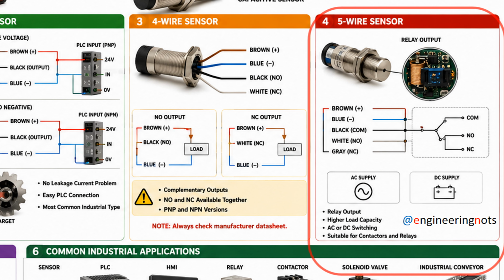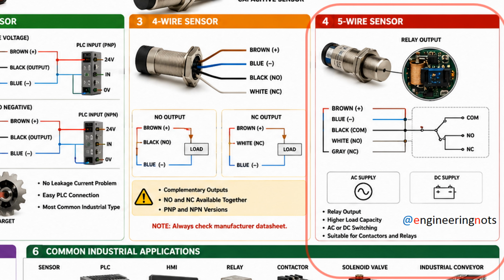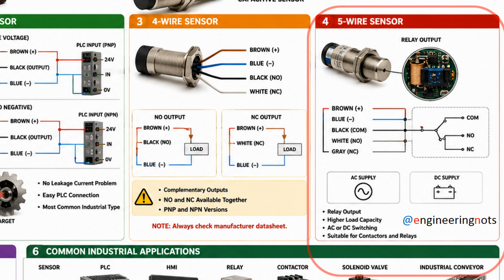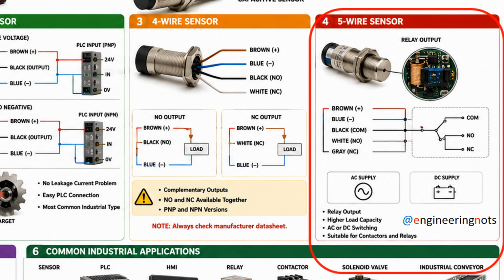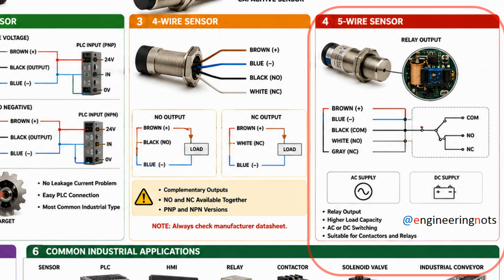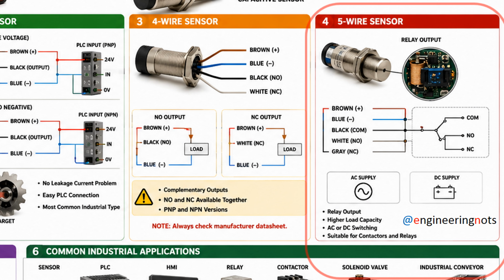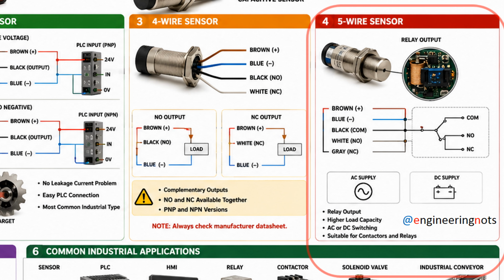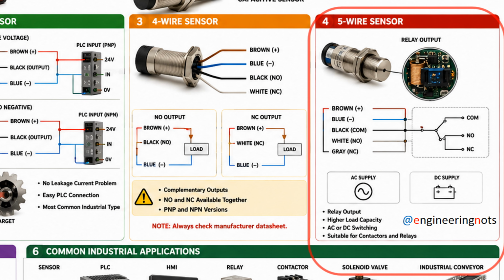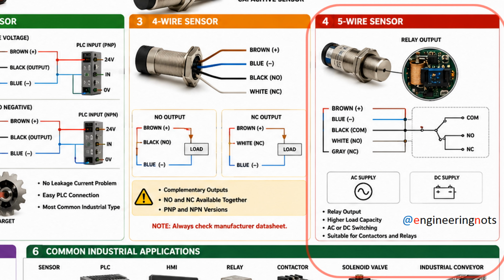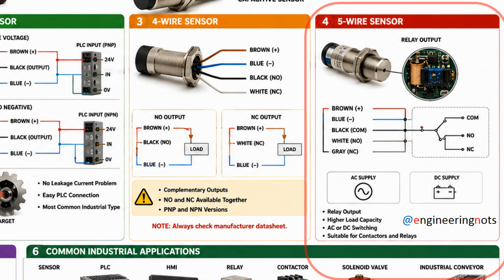Major advantage. A relay output can switch different voltage levels. For example, 24 volts DC, 48 volts DC, 110 volts AC, 220 volts AC. However, the manufacturer's datasheet should always be consulted for the exact ratings and specifications.